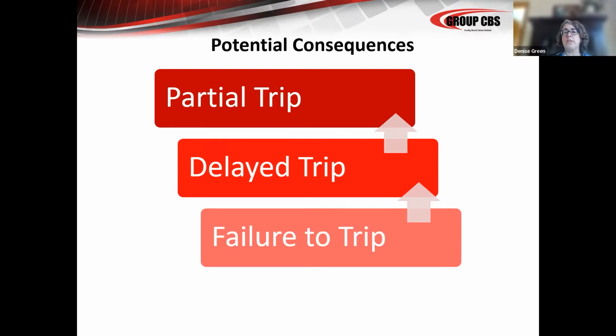The very most dangerous one that is directly related to breaker maintenance is if a breaker partially trips. So if the trip unit gets the signal, it tells the breaker that there's a problem, the actuator gets actuated, the trip bar gets hit, and the breaker only partially opens, you run the risk of the contacts still being close enough that you have not bridged the gap that voltage can jump, or that the arc doesn't extinguish because your contacts are very close. And now you have a situation where you have the generation of ionized air. And once the ionized air that's generated at that particular point goes to another phase or phase to ground, now you have a full arc flash event. And that can happen very easily when a breaker does not trip all the way.